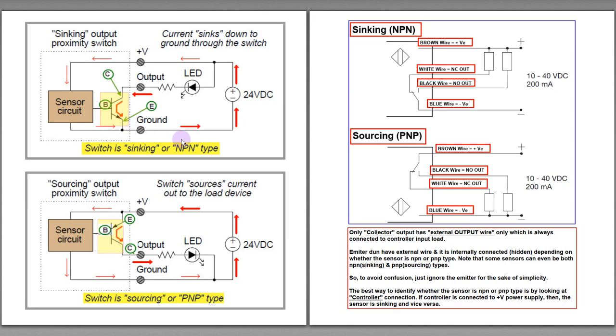Since this is a sinking or NPN type switch, the E emitter is internally connected to the negative V or ground wiring. The C or collector output is always connected to the load. The load can be anything — a PLC input, an electronic recorder, or any controller — as long as it has resistance, it is a load.